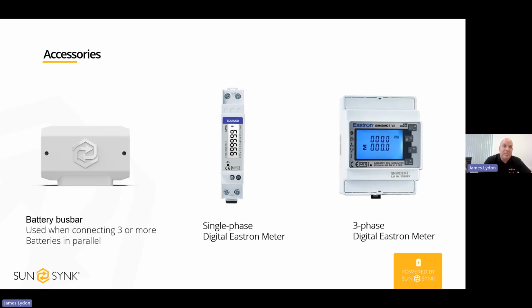But if you're connecting more than 2 batteries, so 3 or more batteries, we always say to use our battery bus bar. Just imagine you've got your inverter and there's 5 batteries connected to it. That first battery is really happy because it's getting all the juice from the inverter. But as we progress down that parallel line, it's quite easy for the batteries to come out of balance. So with our bus bar, you'd have all your batteries connected to the bus bar, on the long positive and negative leads that come with it. Each bus bar will take 5 batteries.